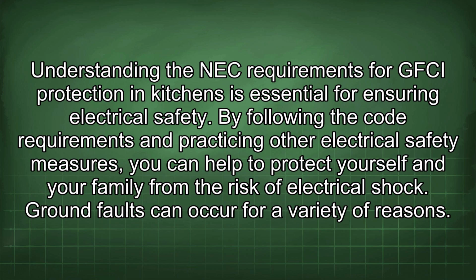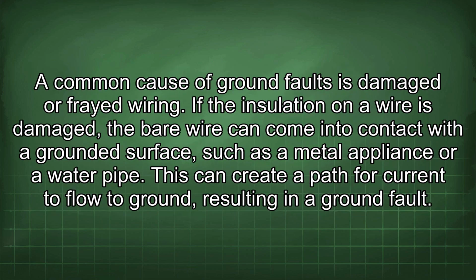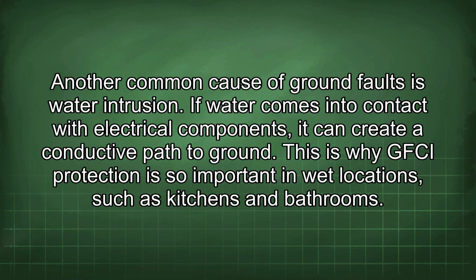Ground faults can occur for a variety of reasons. A common cause of ground faults is damaged or frayed wiring. If the insulation on a wire is damaged, the bare wire can come into contact with a grounded surface, such as a metal appliance or a water pipe. This can create a path for current to flow to ground, resulting in a ground fault. Another common cause of ground faults is water intrusion. If water comes into contact with electrical components, it can create a conductive path to ground. This is why GFCI protection is so important in wet locations such as kitchens and bathrooms.